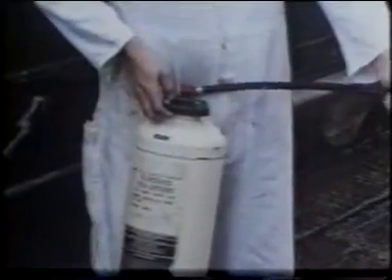If the liquid temperature is high and the surface is penetrated, the water content in the foam will rapidly expand into steam within the burning liquid and may produce a boil-over effect, such as you see in the extreme case when water is directed straight onto the burning oil.